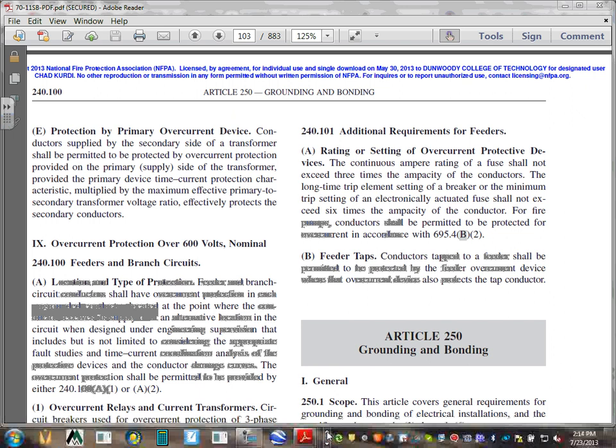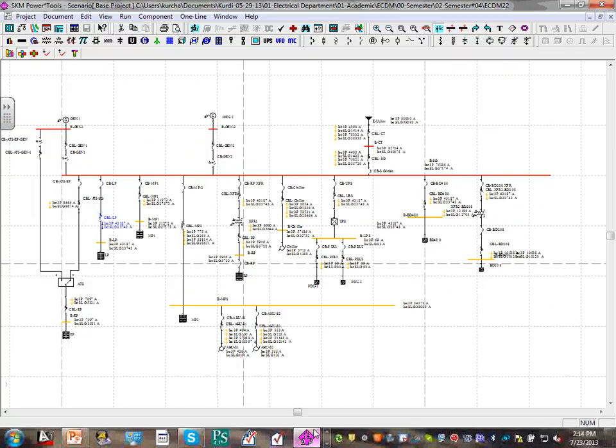You always size them, because we're protecting them from short circuit, our main intention in the high voltage. Okay, so my understanding is that when it comes to the medium voltage, the full load current is really the least of your issues.